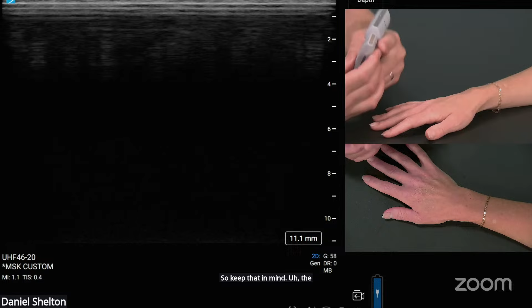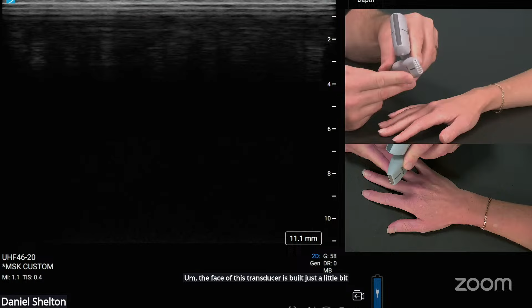The field of view is going to be a little bit different, but there is something different about the head of the transducer. You'll notice a concavity there. So the face of this transducer is built just a little bit different, and it allows us to catch very extreme detail in the near field.